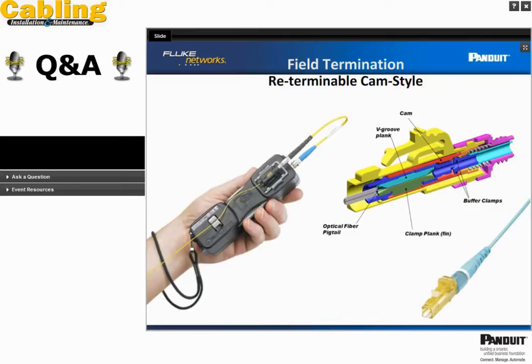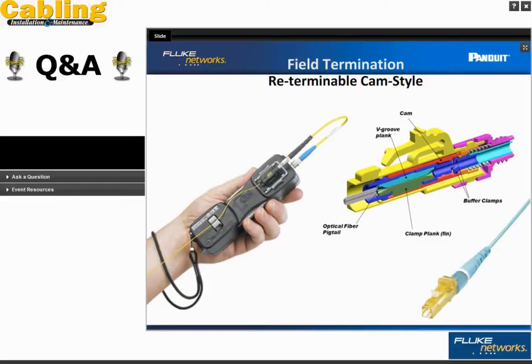Yeah, I think it does somewhat, but you have to look at it like the ultimate test, the acid test, is the link test. So even with that, you will get failures. Things that look good visually or pre-measured as visually good can fail in the link, and conversely, ones that look bad could actually be good. So the best practice is to rely on the link test as the acid test.